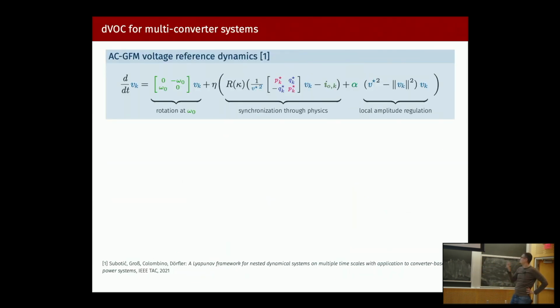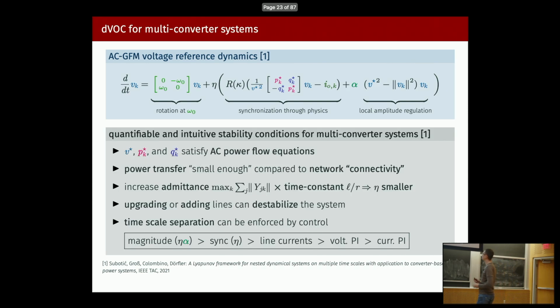To give you an idea of what these look like, here is an equation where we form the reference voltage that the converter imposes onto the grid. This is an oscillator written in Euclidean coordinates, as a two-dimensional vector. The first term makes it go around at the nominal frequency. Then you measure the current injection into the grid and compare it to some reference, which is what allows you to synchronize. So if the power or current injection into the grid isn't what you want, you change your voltage to get closer to the injection you want. The last term does some voltage amplitude regulation.